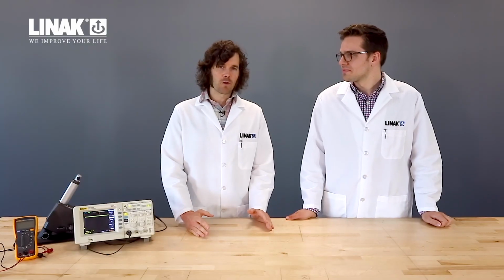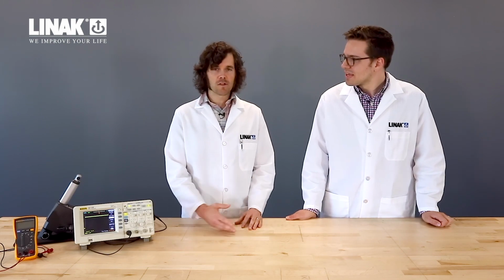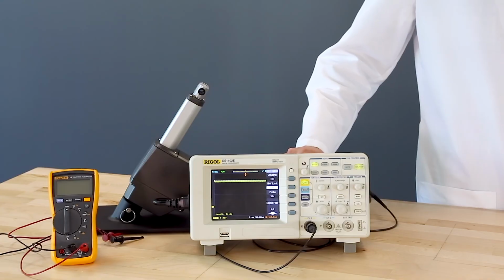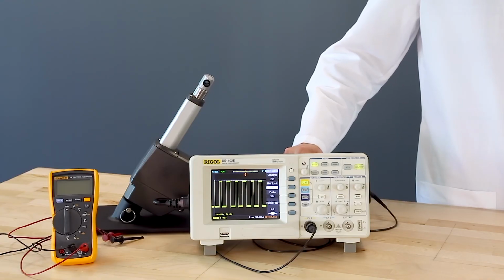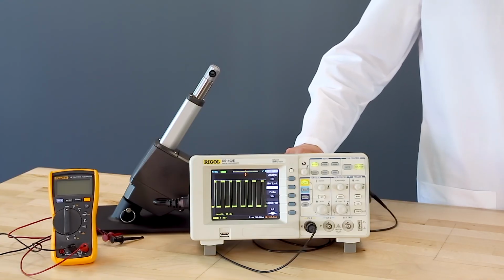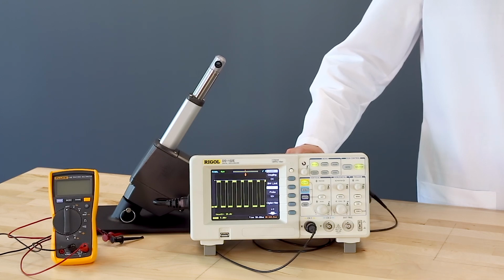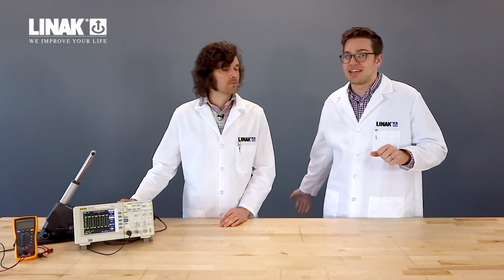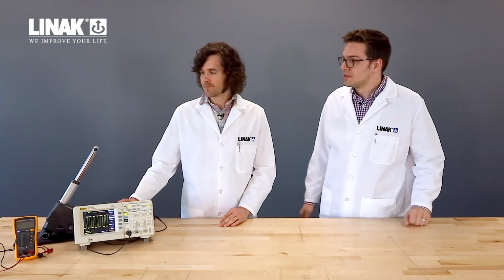So for relative positioning, many of our actuators are equipped internally with the Hall effect sensor, which is also known as an encoder. It sends out pulses that you can integrate to your system, shown here on the oscilloscope. Yeah. These pulses are a lot like the rungs in the ladder example, and they're accurate like them too. If, say, for example, each pulse is related to 1 foot on that ladder, counting the rungs is going to be a lot more accurate than looking down and taking a guess at how high off the ground you are.